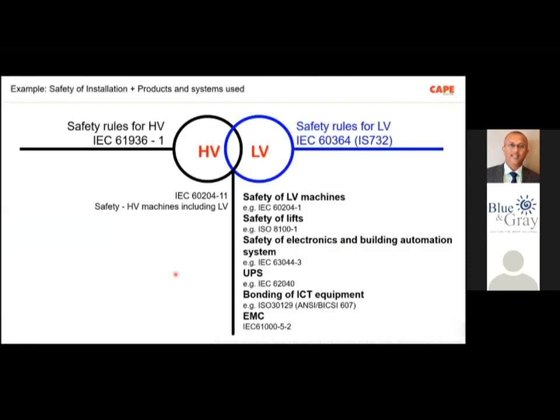Now, what do we mean by design, erection, and testing? Testing, the last one, means it is not only testing, it is called verification, consisting of inspection and testing. I'm just showing you a picture to inform you that in your electrical installation, probably you will have a high voltage system. In that particular case, you must follow the rules of IEC 61936 Part 1. An equivalent Indian standard is already on the way. Probably very soon there will be an Indian standard for this case. On the low voltage side, we are supposed to follow 60364, which is nothing but IS 732. Actually, it is not only IS 732, it is IS 732 plus the National Electrical Code of India.